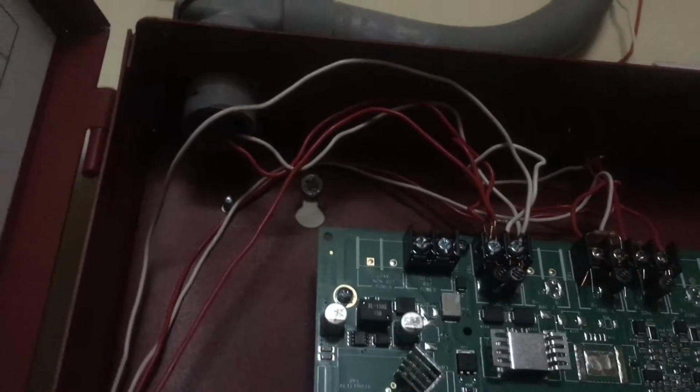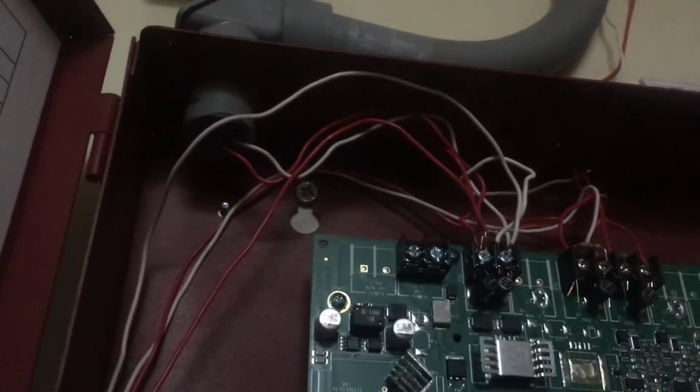Over here we have resettable power, which is basically constant power pretty much. Non-resettable power means you can't reset. It's kind of confusing, but you really don't need to use that. But here's what you do use: NACs. This panel only has one NAC, so it's a 2-wire panel. Now the NACs go to your alarms. It stands for Notification Appliance Circuit, and that's where you put your connections. Make sure you got it wired correctly.